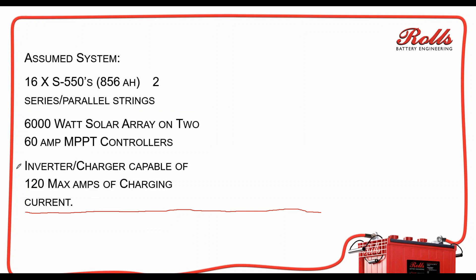Here is the assumed system. On this specific system, we've got 16 S550s — so it's an 856 amp-hour battery bank. They're two series-parallel strings: two parallel strings of eight batteries for a total of 16 batteries. We've got a 6-kilowatt PV array on two 60-amp charge controllers, and we've got an inverter-charger capable of about 120 amps of charge current.